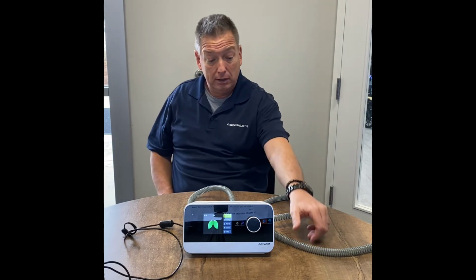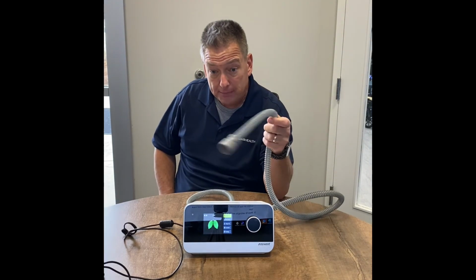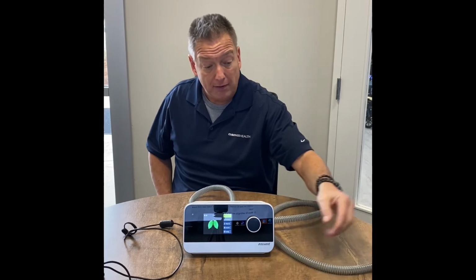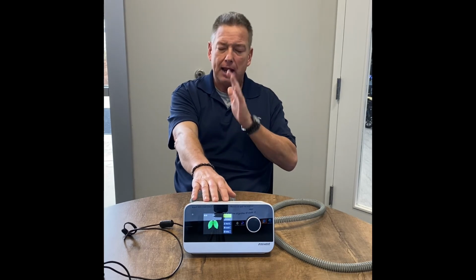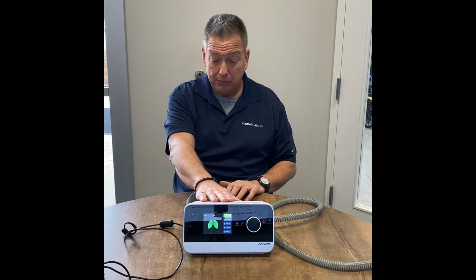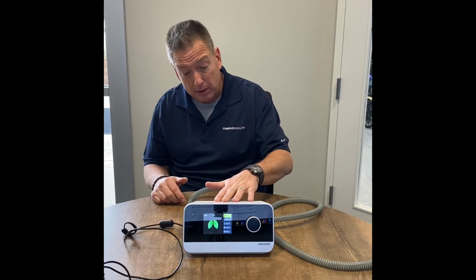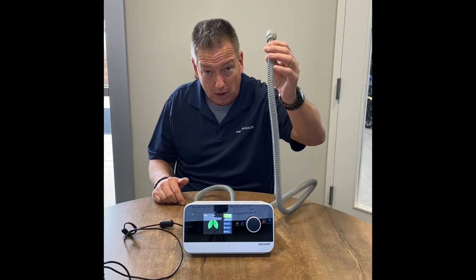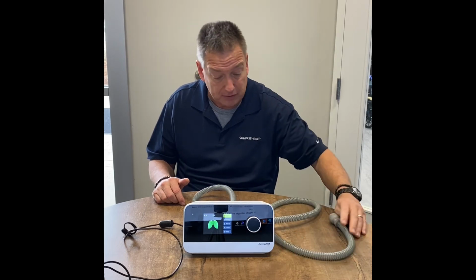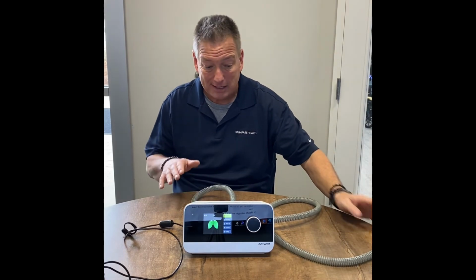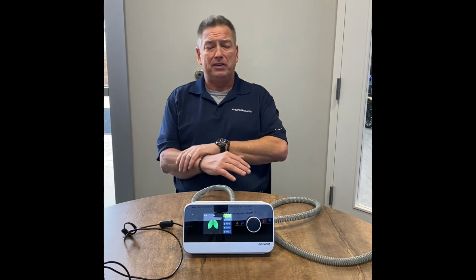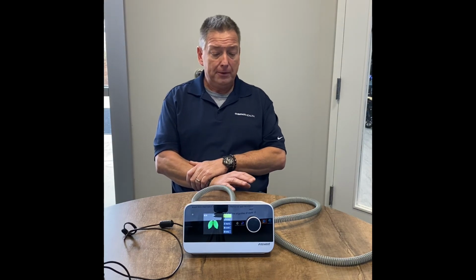It does have a setting for tube type. So if I'm using, it defaults to the 15 millimeter, right? Because that's what it comes with. But if I wanted to use a 22 millimeter, normal size one, it actually is designated as a 19 millimeter in the machine. So if you use a larger tube, you want to put it on 19 millimeter. If you put it on the slim line, you want to put it on 15 millimeter. The length of the tube, it doesn't matter. It can auto adjust for that. So whether it's 6 feet, 8 feet, that really doesn't matter.